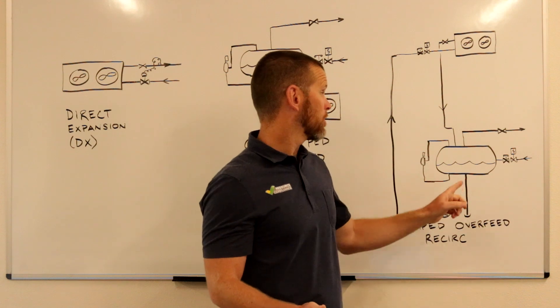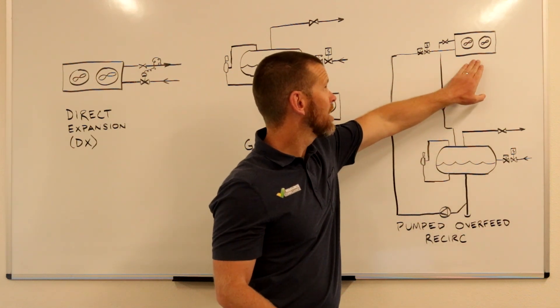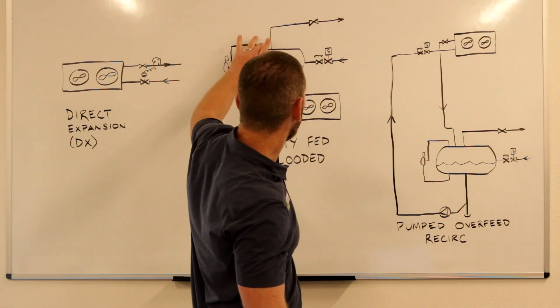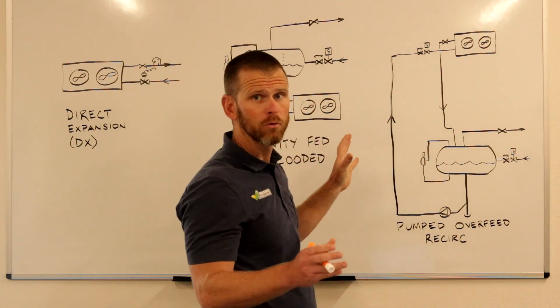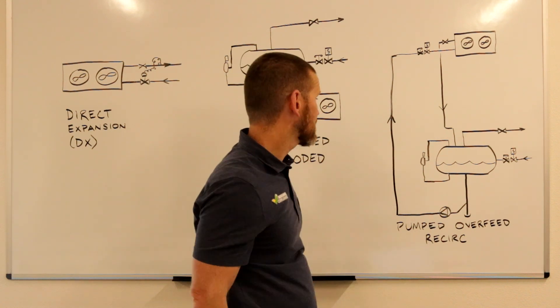The other advantage of this is you can have one recirculator vessel that could feed many, many evaporators. So you don't have to have a whole bunch of surge drums like you might have to in a flooded system. So those are two advantages of this system.